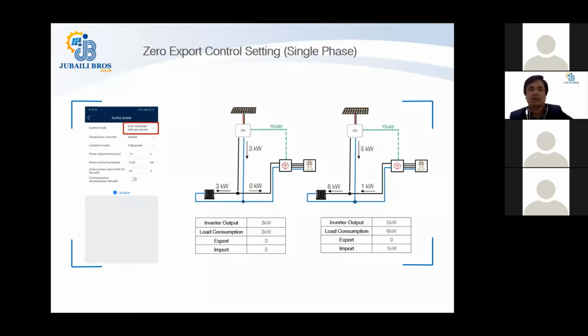Zero export control setting with the single phase. If you have a single phase inverter, which is the 2, 3, 4, 5 kilowatt of the Huawei SUN2000L series, you can do the zero export control. In such a scenario, if the power being generated is 3 kilowatt and the load is 3 kilowatt as well, all the power will be fed to the load.